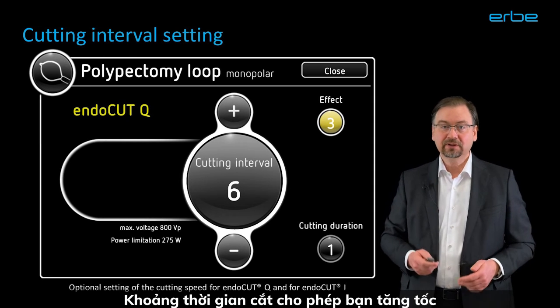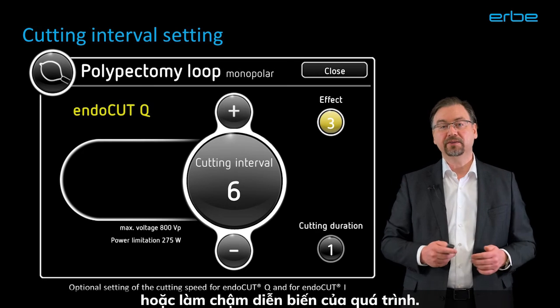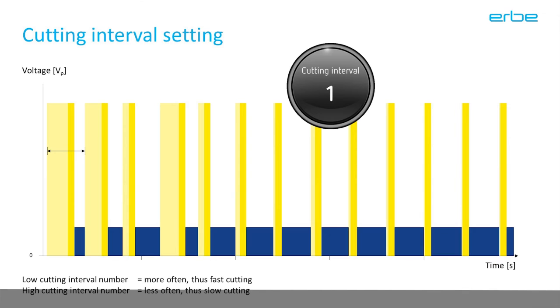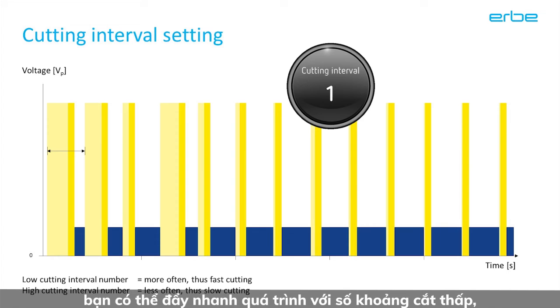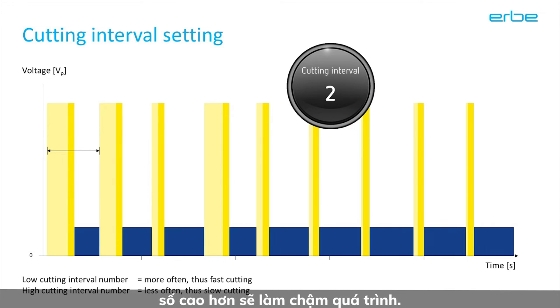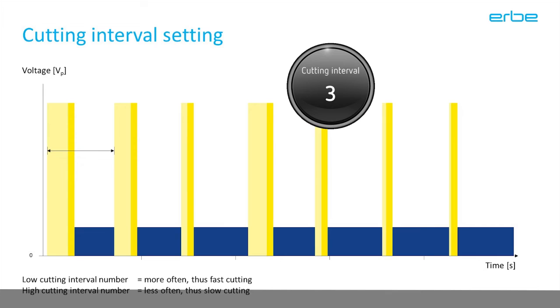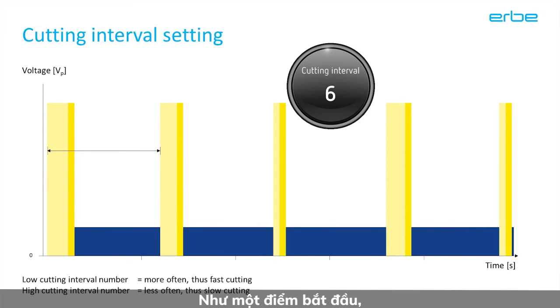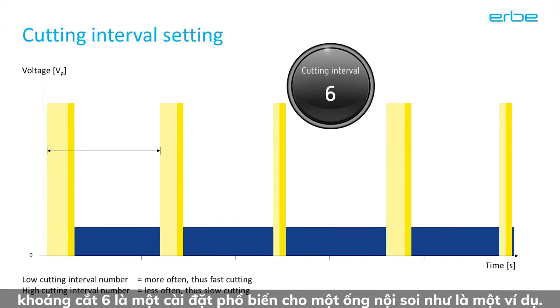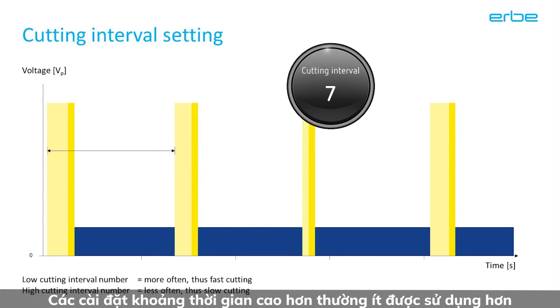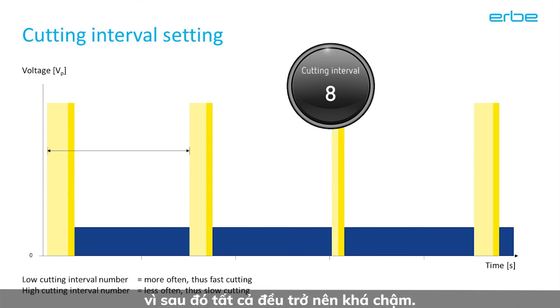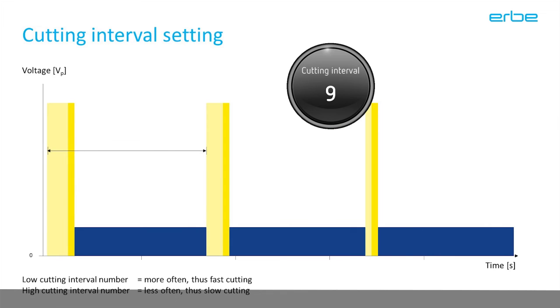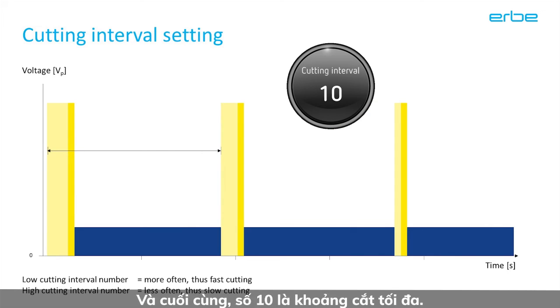The cutting interval lets you speed up or slow down the course of the process. There are 10 increments. You can accelerate the process with low cutting interval numbers. Higher numbers will slow it down. As a starting point, cutting interval 6 is a common setting for an endoscopy snare, just as an example. The higher interval settings are less often used, as it all becomes quite slow then. And finally, the 10 is the maximum cutting interval.